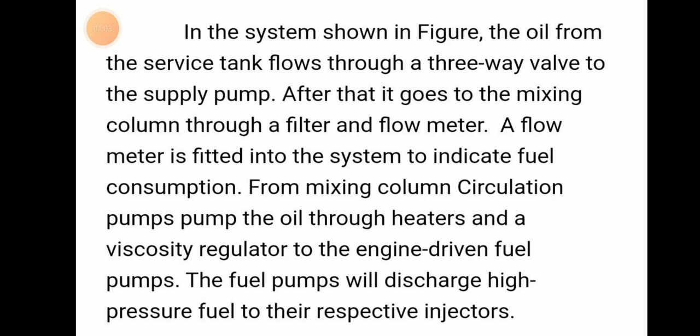From the mixing column, circulation pumps pump the oil through heaters and viscosity regulator to the engine driven fuel pump. The fuel pump will discharge the high pressure fuel to the respective injectors.